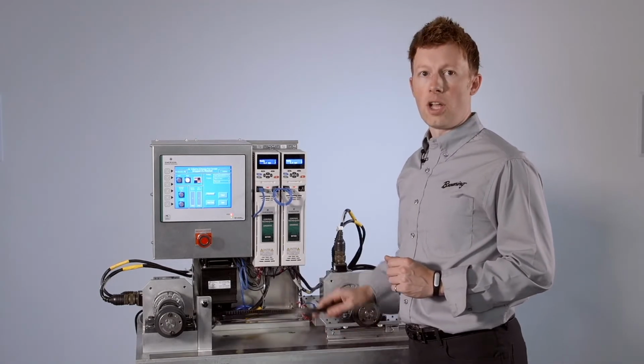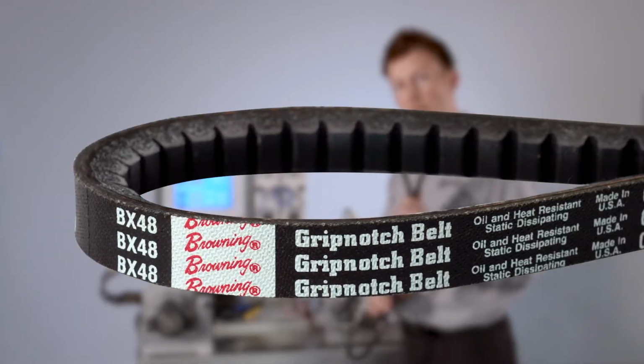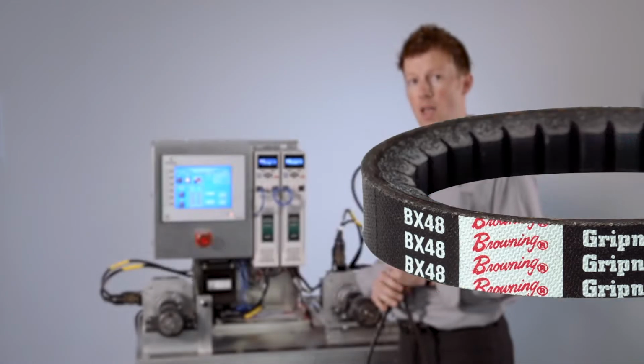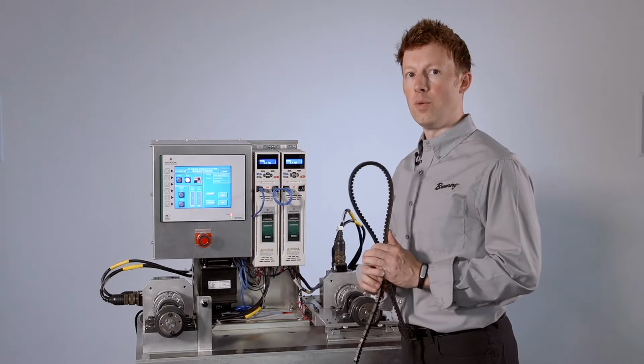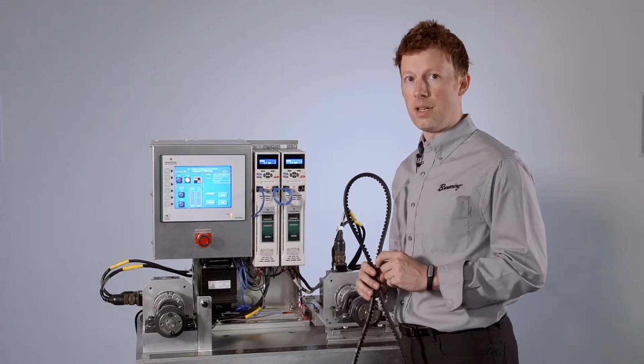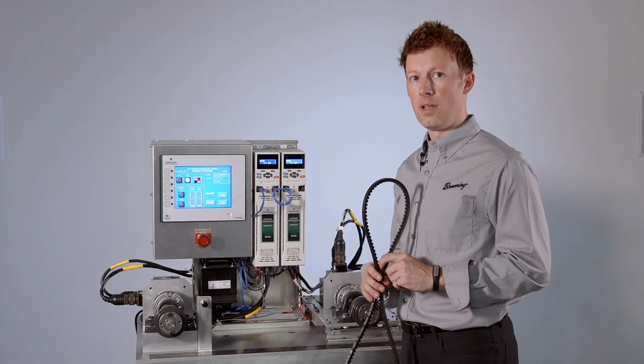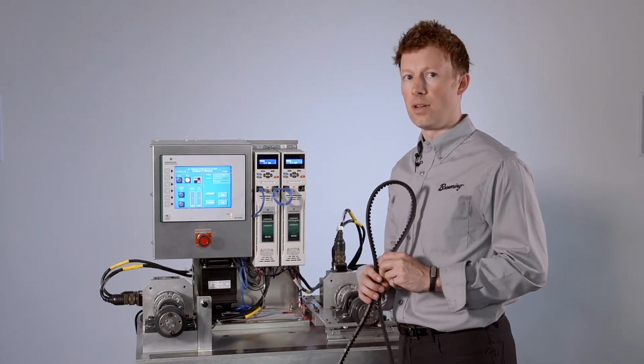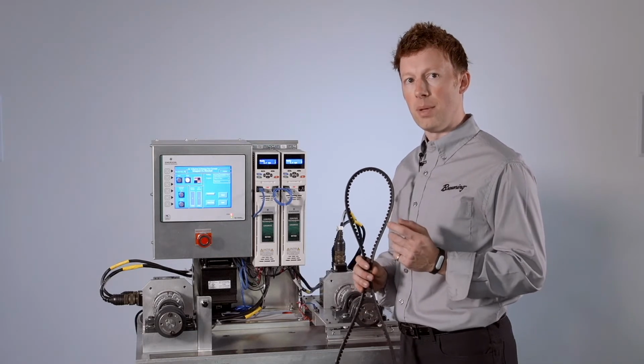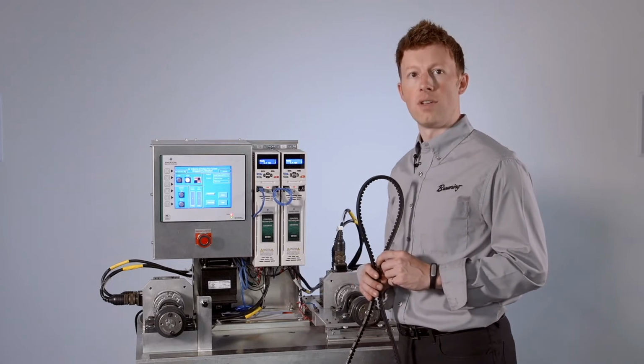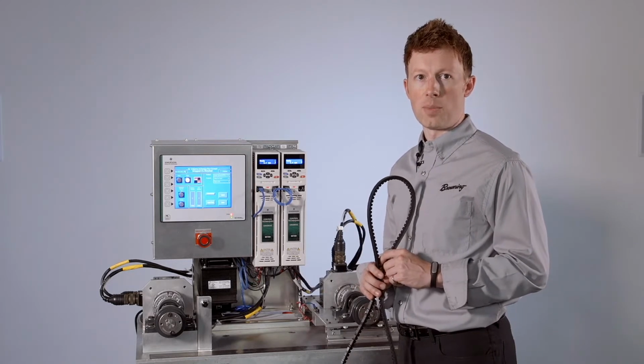Now we're going to install our notched belt. These belts have a peak efficiency of 98%. That 3% gain in efficiency will be seen in a reduction of the motor energy and an increase in the CFM produced. They run cooler, so they last longer, and they're much stronger, so that can give us an ability to optimize the design of a drive based on how much horsepower they can transmit.